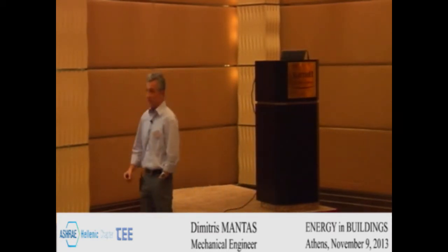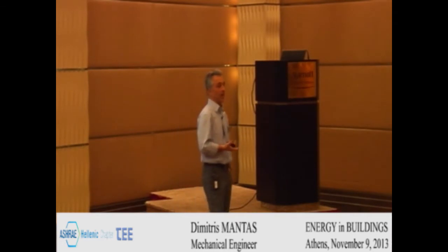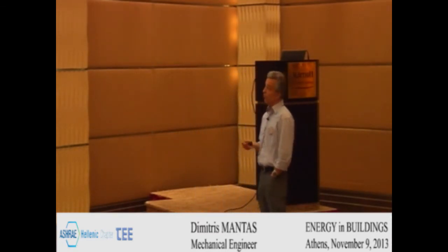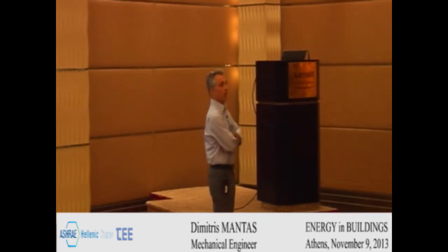This system is impacted. What is difficult to understand is the difference in the use of hot water, which is usually one of the most predictable consumptions. We don't usually expect surprises, and it is quite surprising that we get 5 times more hot water used. The only thing I can say is that something is happening there. The systems do not collaborate or are not very well regulated, although this is a very good building. And of course, the user, God knows what is happening there, how they use it, how they waste the hot water.